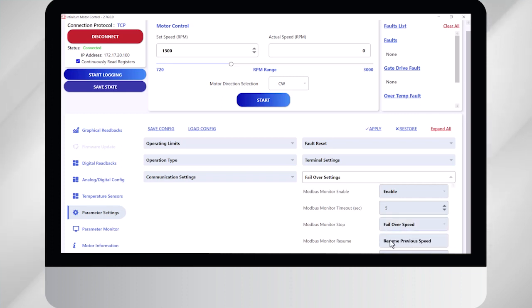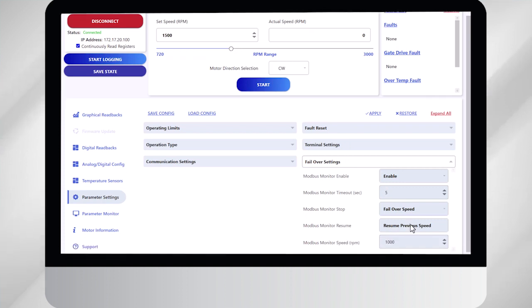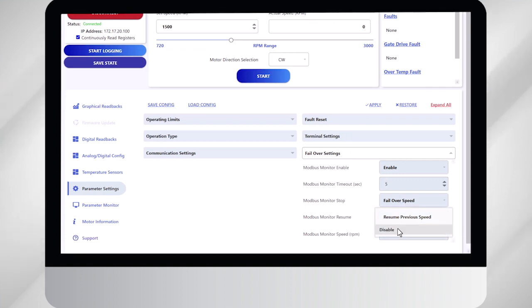The next button is what do you want the motor to do if it resumes communication? The options here are to go back to the original speed, which in my case is 1,500. Or if you leave it disabled, it'll go to this new speed and maintain that indefinitely.